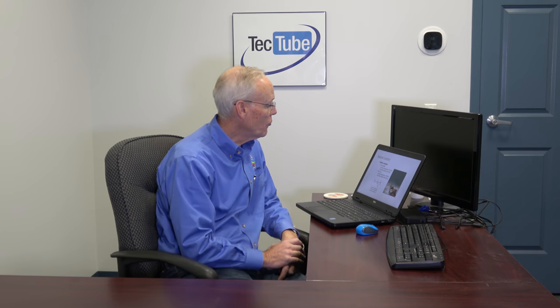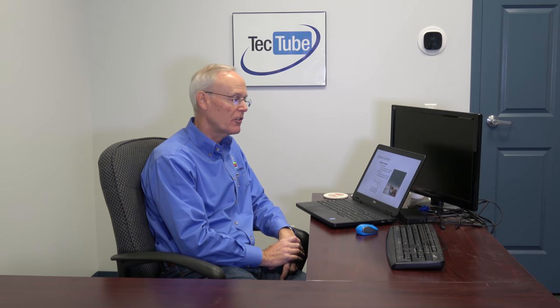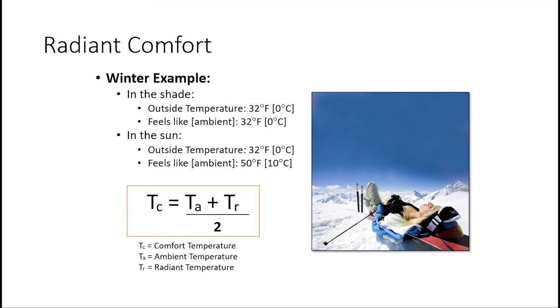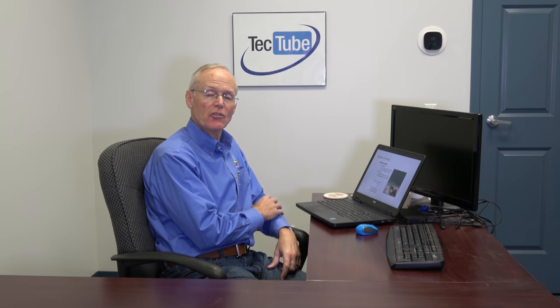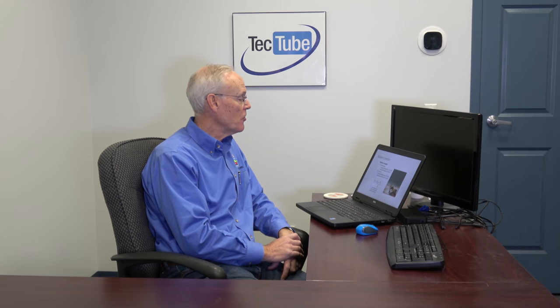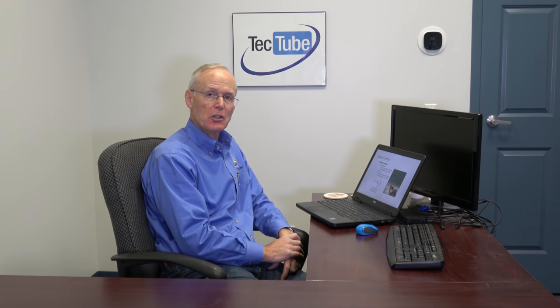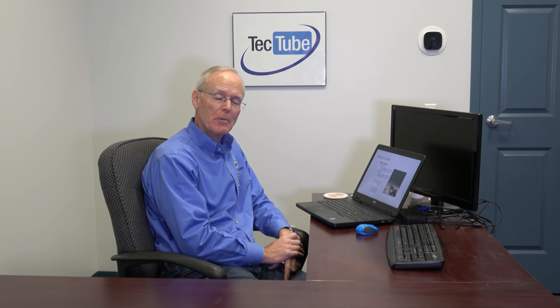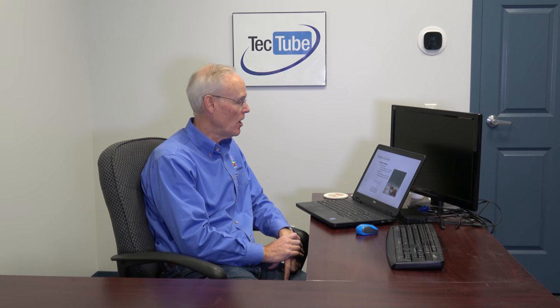One of the new formulas or concepts I'm going to introduce is the concept of comfort temperature. We all know that infrared works off of heating things instead of air. You have an ambient temperature — that's the TA — and then you also have a radiant temperature, which is what it feels like on your skin. The average of those two equals comfort temperature. I want you to remember this formula because it comes into play a little bit later on.